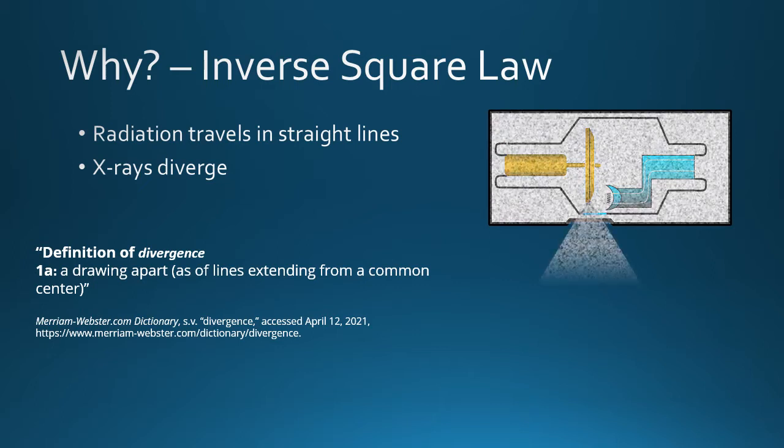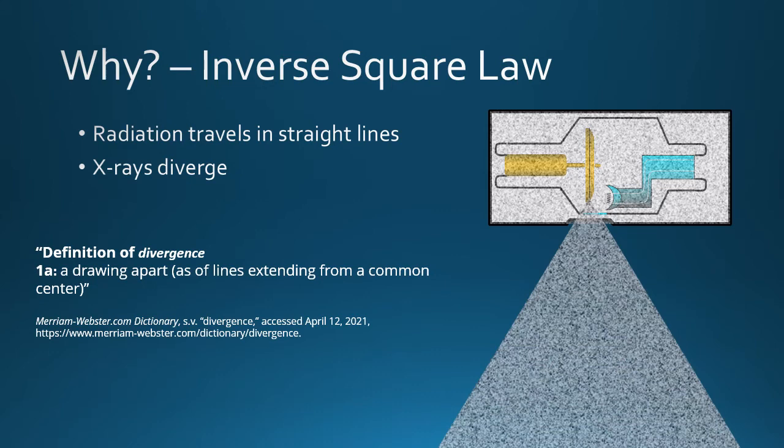Here is an x-ray tube surrounded by a lead-lined housing with a hole — the tube port — where the x-rays can escape the housing. First, radiation fills the housing, then escapes the tube port. The radiation is then shaped by the collimator into a rectangular or square field of radiation. Note that the field of radiation widens, or diverges, as it travels along its path.